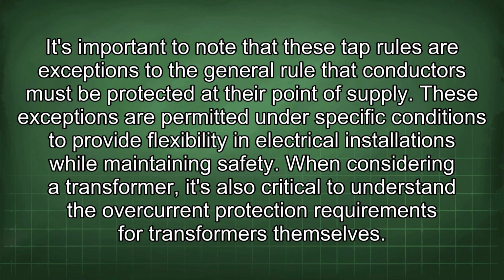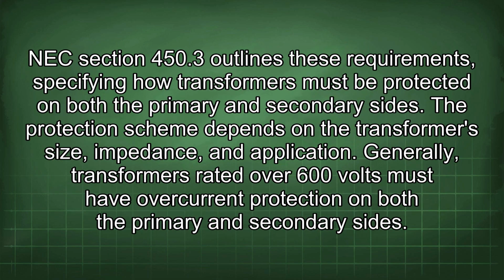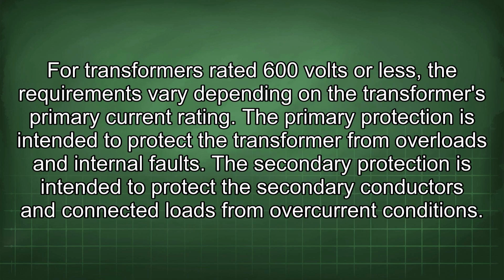When considering a transformer, it's also critical to understand the overcurrent protection requirements for transformers themselves. NEC Section 450.3 outlines these requirements, specifying how transformers must be protected on both the primary and secondary sides. The protection scheme depends on the transformer's size, impedance, and application. Generally, transformers rated over 600 volts must have overcurrent protection on both the primary and secondary sides. For transformers rated 600 volts or less, the requirements vary depending on the transformer's primary current rating. The primary protection is intended to protect the transformer from overloads and internal faults. The secondary protection is intended to protect the secondary conductors and connected loads from overcurrent conditions.